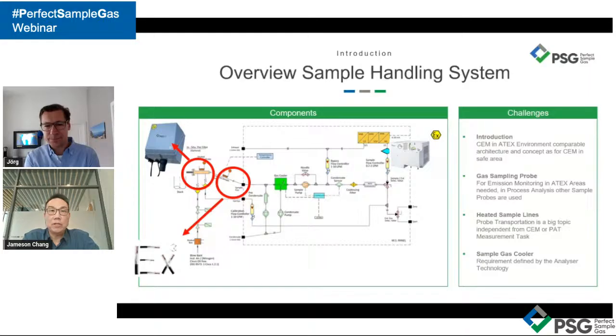Yes. In fact, I just want to say one word about the heated line. There are so many things I would like to share, but we always call it the most underestimated item, the heated sample line, with its long surface area. There are so many heated lines available in the market. And one important factor when you purchase an analytical heated line, and I just mentioned the word analytical, is the material that we use, whether it's PTFE or PFA. These are called analytical lines, where we have to consider the adsorption and desorption of the gases. So it is very important. At the end of the day, we want to measure a representative sample.